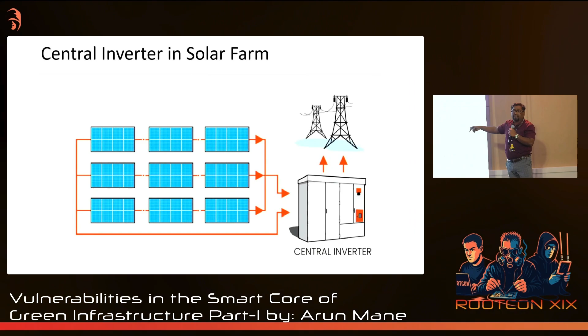So in brief, you can see the parallels in series, they are connected. The solar panel connects to the central inverter, and then it connects to the infrastructure through some sort of Modbus communication. Usually in Chinese products, they use Modbus rather than any other communication like DNP3. That connects with the SCADA infrastructure in this case.